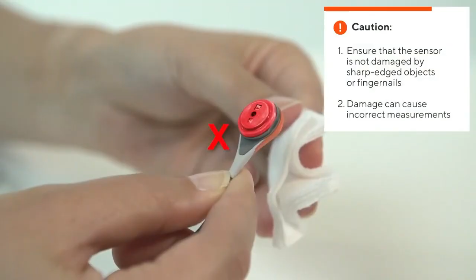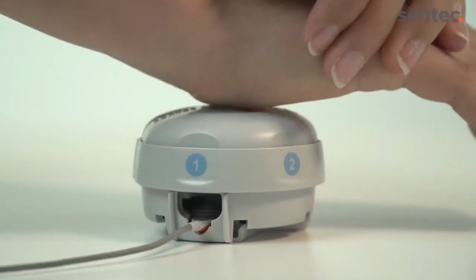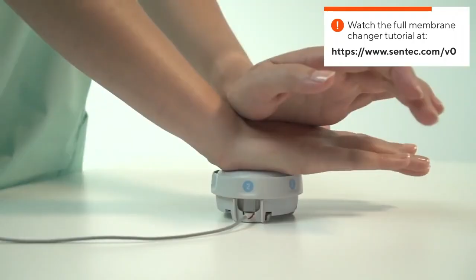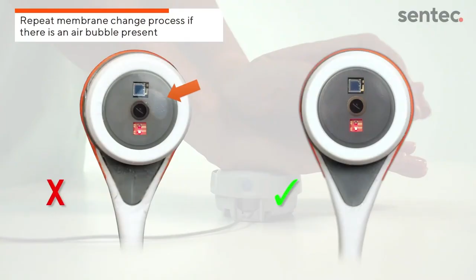Once the sensor is dry, you will need to replace the membrane. Carefully insert the sensor into the membrane changer without touching the exposed sensor surface. Make sure the sensor is aligned correctly. Proceed with the membrane change as usual with the alternating pressing and turning steps. Make sure that there are no air bubbles and verify that the membrane is correctly seated on the sensor.